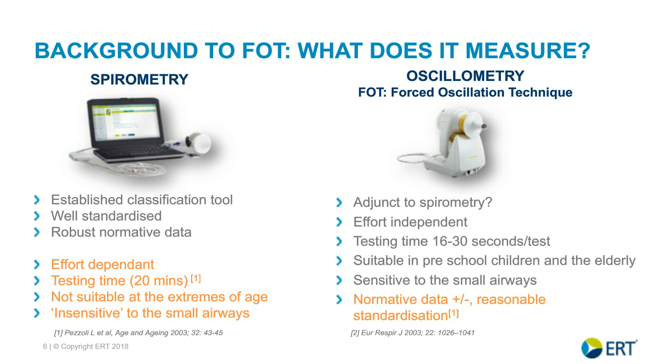The technique is proven to be valid and useful in preschool children, and it's useful in other populations that I mentioned that may be difficult to test with spirometry, particularly patients that are elderly, tracheostomized patients potentially, but also patients that are having acute and severe exacerbations. And furthermore, as you'll see in my talk, there is evidence that the FOT technique is sensitive to the peripheral airways. There's mounting evidence. There is a disadvantage, which is that FOT currently lags some way behind spirometry when it comes to normative data, although efforts are underway for standardization. I'll mention that in my talk.